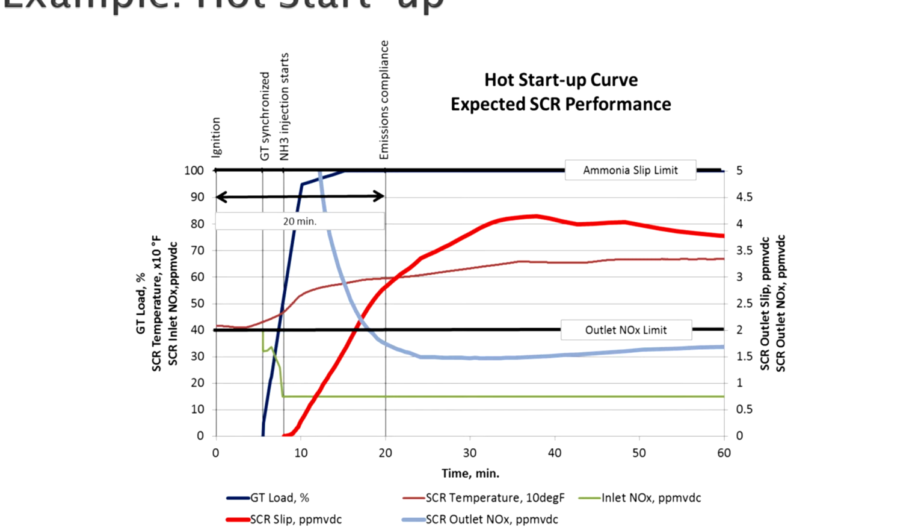So you've got this combination of high NO2, high NOx, transitioning down. So you'd wind up with this large amount of ammonia you'd have to come in with early, trying to get the SCR up to performance, get the ammonia absorbed on the catalyst and start to reduce. And then as all of a sudden that turbine load's coming up, its NOx is dropping, probably the NO2 ratio is dropping off. So controlling that transitionary period is going to be very complicated.